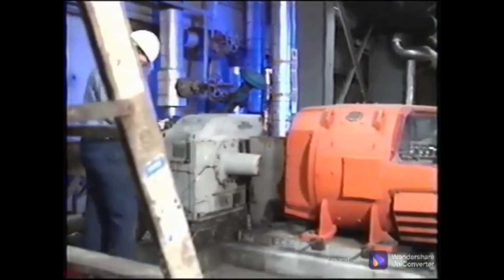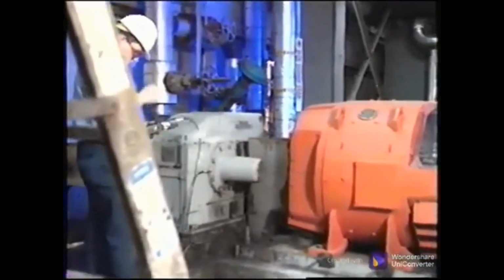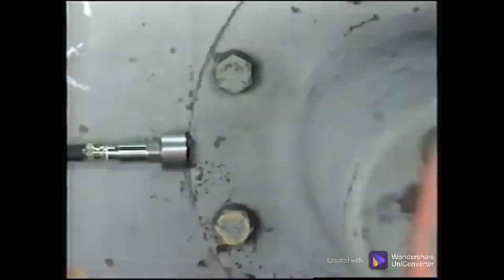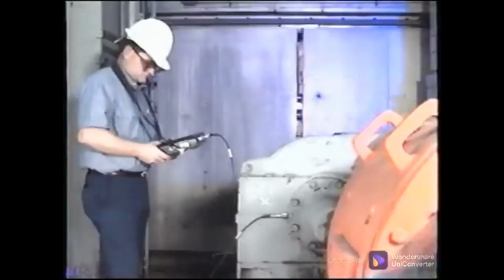In routine PDM programs, it is common to detect problems with gear drives using the amplitude of the gear mesh frequency alone. In this case, the key is the change in amplitude. Although there may not be a serious problem with the gears, other problems such as bearing wear, misalignment, and bad coupling can affect gear mesh and lead to gear degradation.